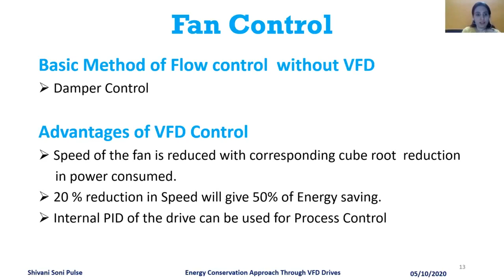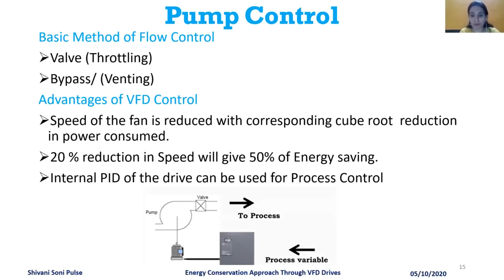In the pump, two methods are generally used in the conventional approach: throttling valves, or venting or bypass valves. But if we take the VFD in the system, in the same way we reduce the speed of the motor, which controls the fan speed and pump speed, and we get 50% energy saving here. Also, the VFD has a PID control feature, so we can utilize PID control parameters in the process systems.